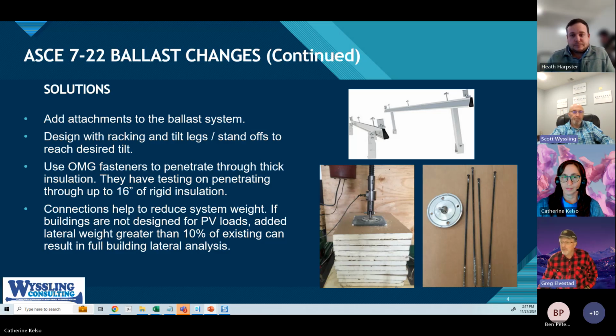Another item to go along with that real quick is the 3741 compliance, which, for those that aren't familiar, is the adjustment to rapid shutdown requirements for solar systems installed on buildings. Traditionally, you need microelectronics installed at each module to shut everything off. There is a provision now for systems to have a design without those electronics, saving a significant amount of money. But there are some specifics related to the way that gets designed, and racking equipment has to be certified for that application. Just bear that in mind as another option.